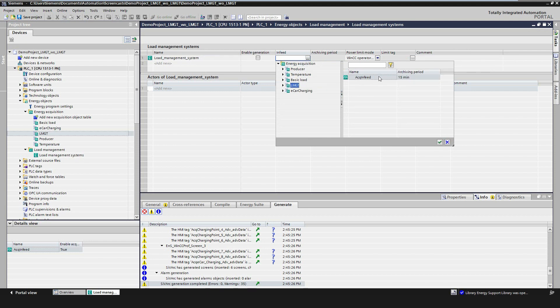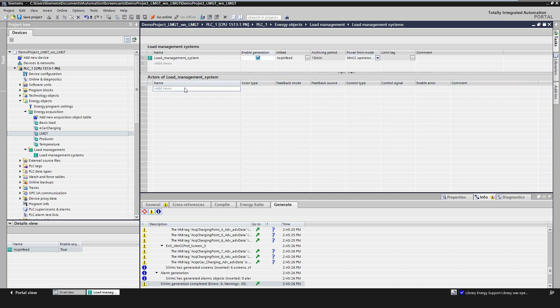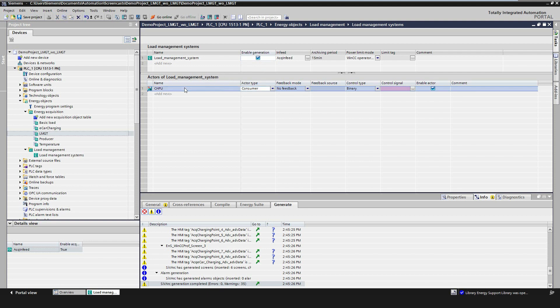The value for the power limit will be configured later. Subsequently, the actors of the load management system can be configured. The maximum number of actors is 999. Currently, there are two types of actors: consumers, which consume energy, and producers, which provide energy.